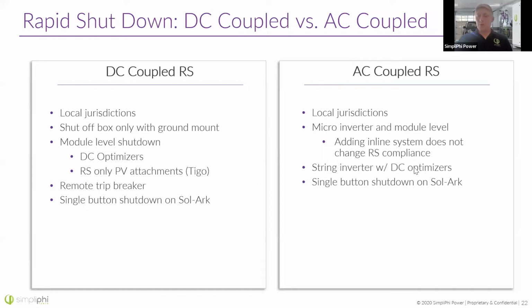Now, with AC coupled PV systems, if you've got an existing array that's grid tied and then you add batteries into it, usually that does not change the rapid shutdown compliance of your PV array. So whatever you've got already, you're probably good to go. You're probably grandfathered into whatever it is you've got up there. But the batteries may or may not require certain rapid shutdown depending on where you are. So mostly they do not. But then again, sometimes you've got to have that single button. So that's something you'll have to look into and consider as an installer before applying for the permit or during the permit process to make sure you meet those requirements.